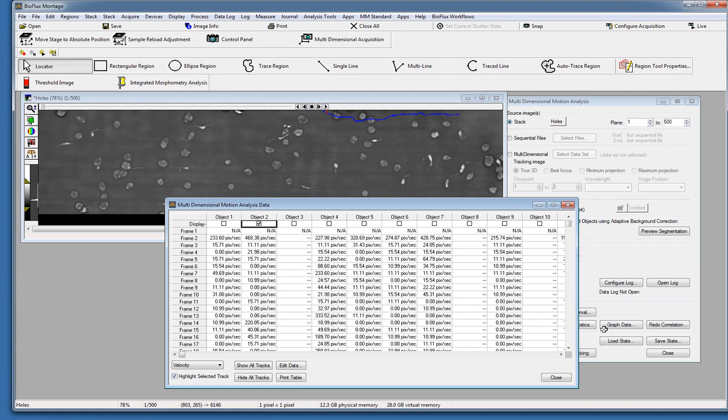Now that's with the low shear plate. With the high shear plate, and these were done with a high shear plate that goes between 0 to 200 dynes, that's not an issue because the cells start out in a wider area and then flow down into the active area of the viewing channel. We haven't calculated this because it's a little bit of a conical shape, but it's several fold less in terms of shear force until it gets to the viewing channel, and then it goes to what's set with the program.